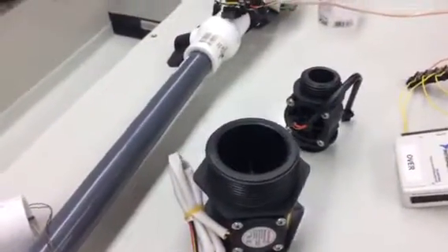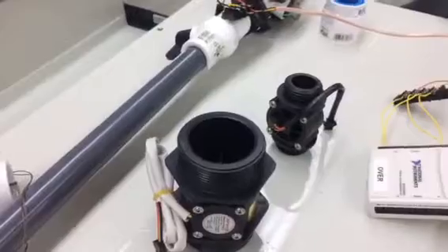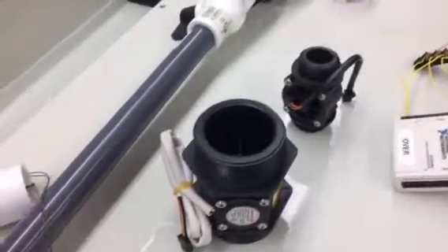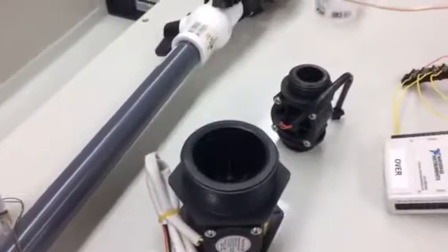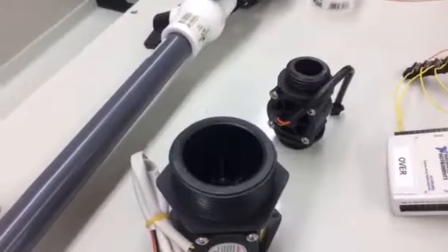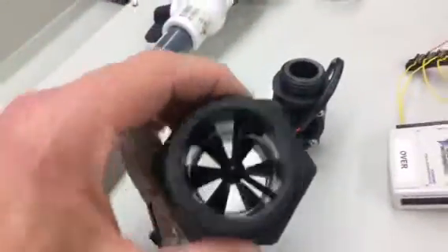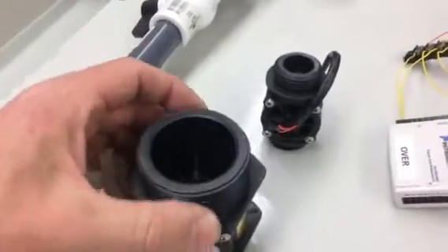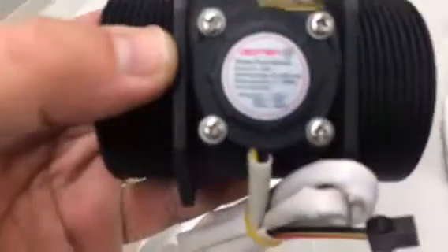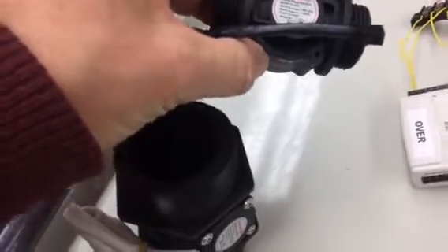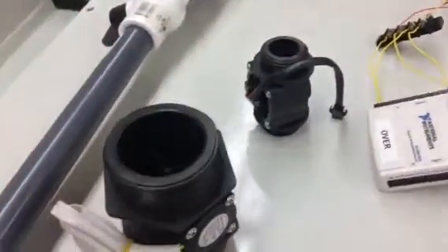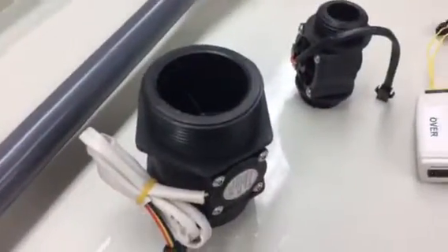Good afternoon. This week we're going to do a lab with flow sensors. These are the Hall effect type. We have them that start at 3/4 of an inch, then a 1-inch pipe size, and all the way up to 2-inch pipe size. They have different flow rates. The highest looks like 10 to 200 liters per minute. This one, if it's on here, is 1 to 60 liters per minute. I think the 3/4 inch ones are about the same.